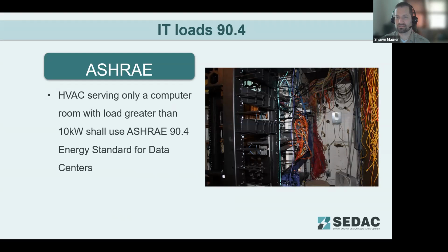For IT closets, ASHRAE has a standard for data centers that is not included in the IECC currently. It's triggered once a computer room has more than 10 kilowatts of IT equipment. It's good to understand where the threshold is between a room with IT equipment and a data center. Buildings commonly have several IT equipment rooms with lower loads. The transition to a data center that has specific requirements in ASHRAE 90.4 is that 10 kilowatt total power requirement.